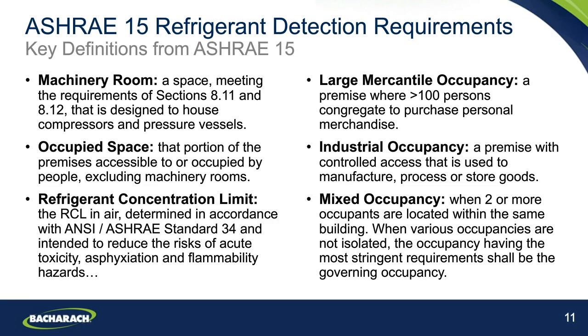A couple of references regarding occupancies. A large mercantile occupancy would typically be what we would define a supermarket or a large grocery store within. An industrial occupancy is a premise which has controlled access and that's used to manufacture, process, or store goods. So this is typically where we would see refrigerants in applications such as food processing and industrial cold storage, and this falls into cold rooms and walk-in freezers within smaller applications as well. Then a mixed occupancy is where we have two or more of these different types within the same space. Key thing there being the most stringent requirements for those occupancies are the ones that come into play for all of them.